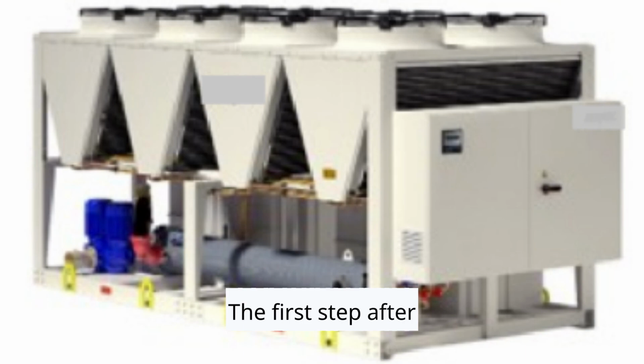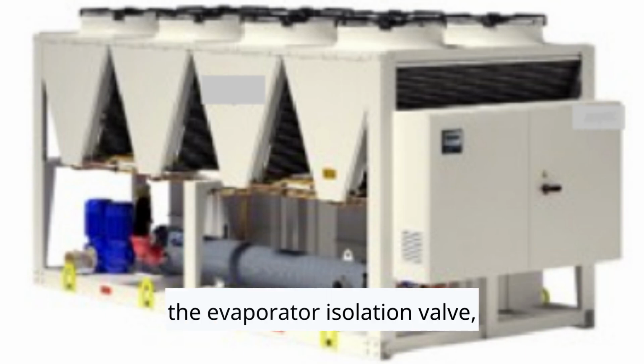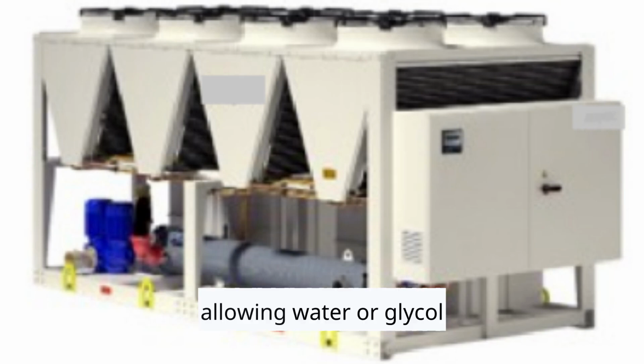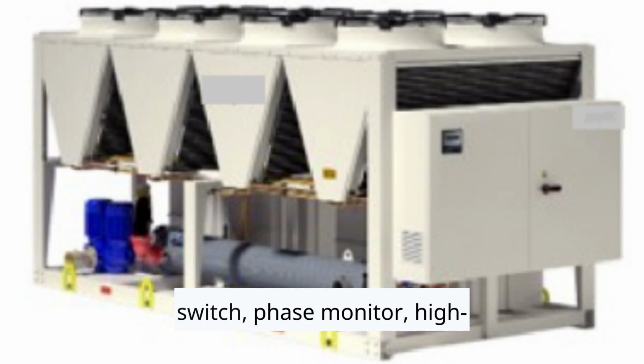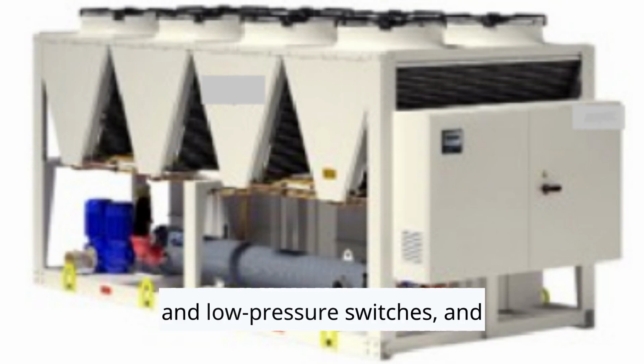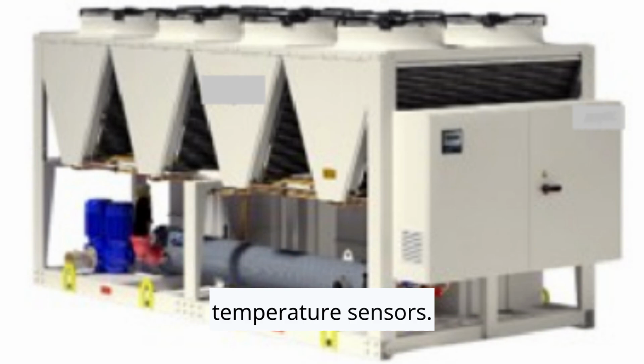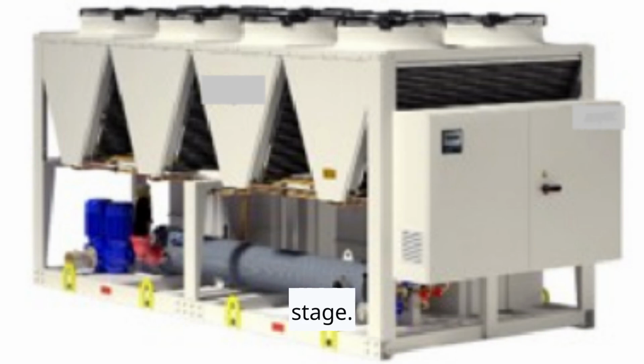Once the unit receives that enable command, it prepares itself for operation. The first step after enable is to open the evaporator isolation valve, allowing water or glycol to circulate through the unit, and at the same time, the controller sends a pump enabled signal. The controller then checks all safety conditions. This includes the flow switch, phase monitor, high and low pressure switches, and temperature sensors. Only when everything is normal will the unit proceed to the next stage.